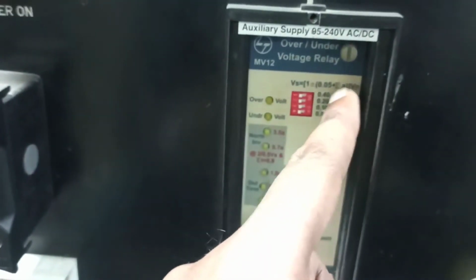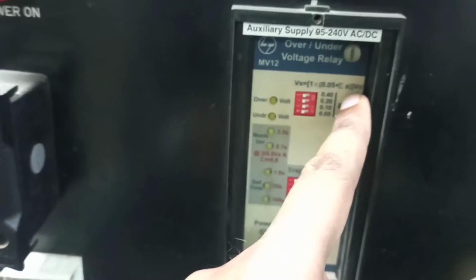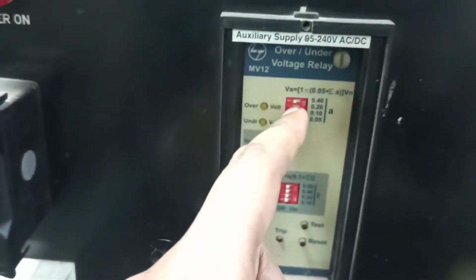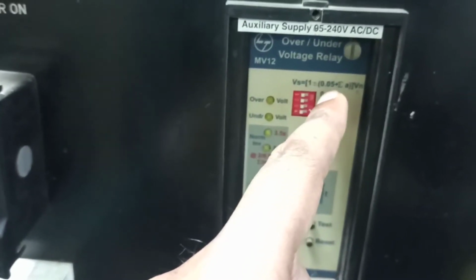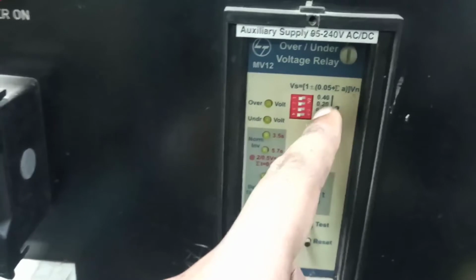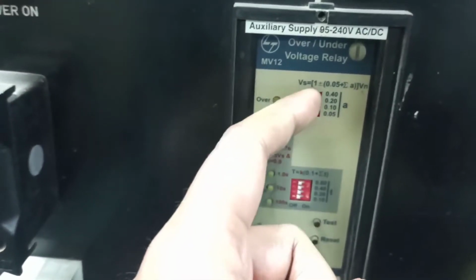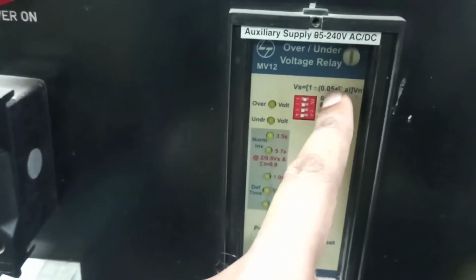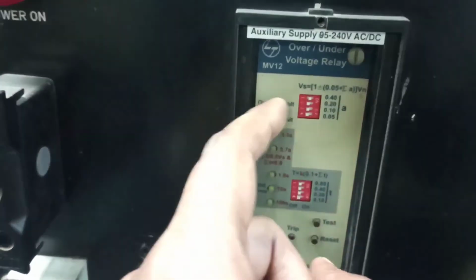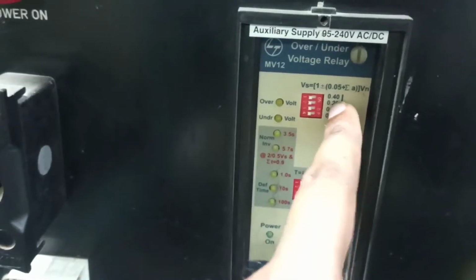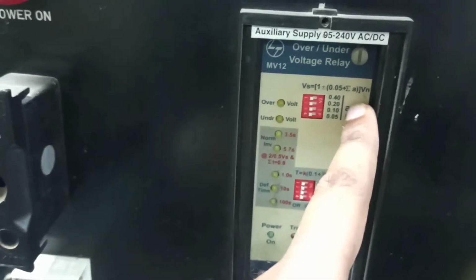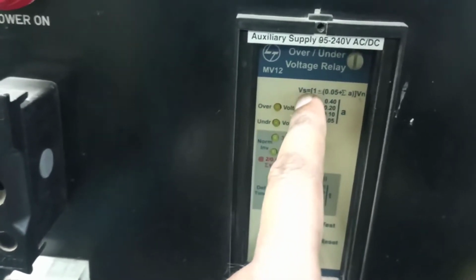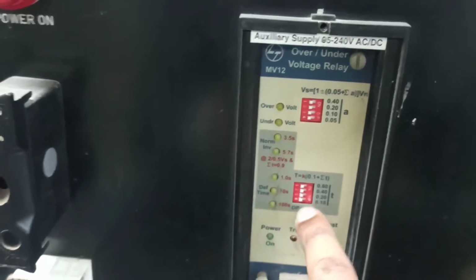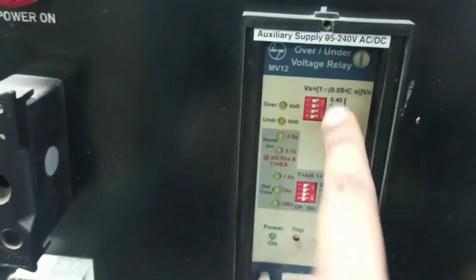Okay, so these are the settings for voltage settings. This is your Vn, your reference voltage, which is 110 volt here. This relay is going to work on 110 volt. This is 1 plus minus 0.05 plus summation of A. A is the setting of these switches of the relay. Whatever setting we turn on, suppose I turn on 0.40, then this is 0.05 plus summation of 0.04. If I turn on two switches, 0.4 and 0.2, then it is 0.05 plus 0.4 plus 0.2. Like this, your reference voltage will come out from this formula, and your reference time will come out from a similar formula.